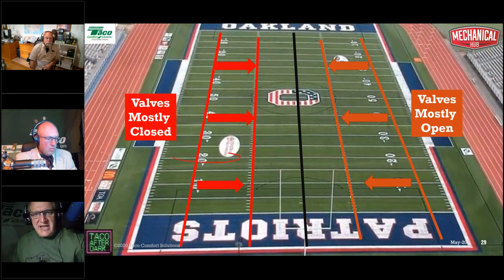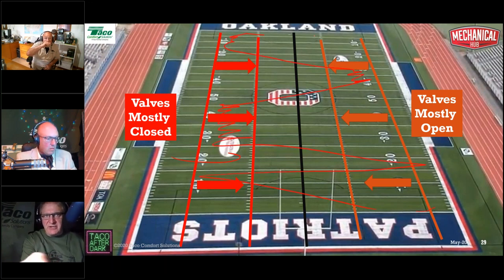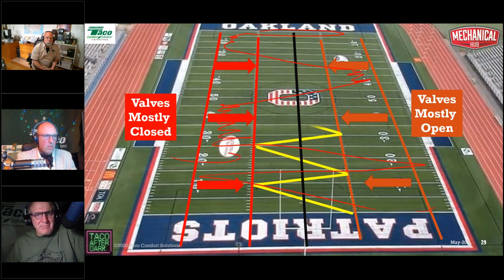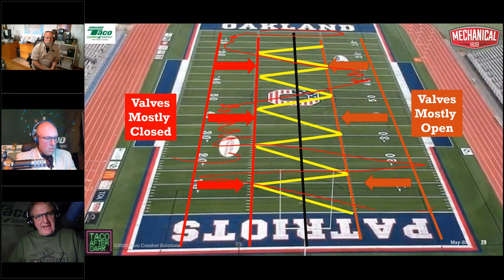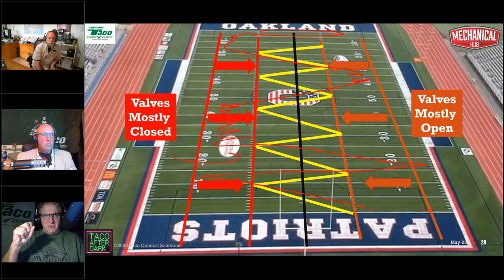Instead of bouncing along like this, spending a lot of time over here, then over here, it's shrinking the field. Now we're bouncing off a much smaller field, and it makes for much more consistent heat delivery. The pump will adjust its speed accordingly to make sure that the TRVs aren't opening all the way and then all of a sudden having to close real quick, opening and closing and opening and closing. I hope that's a good visual for what we try to accomplish with Active Adapt.